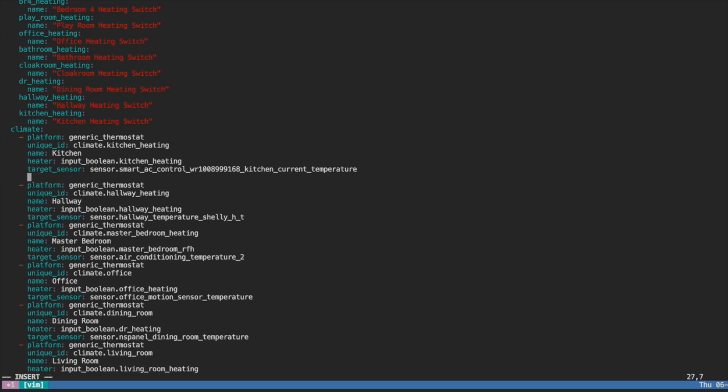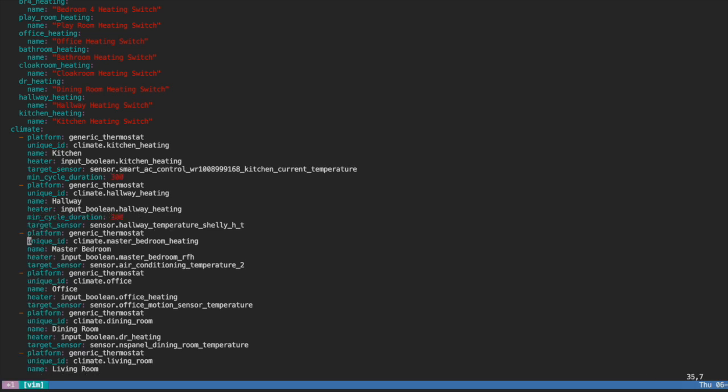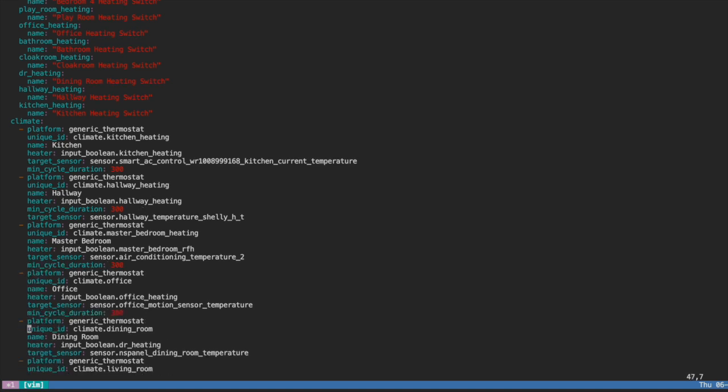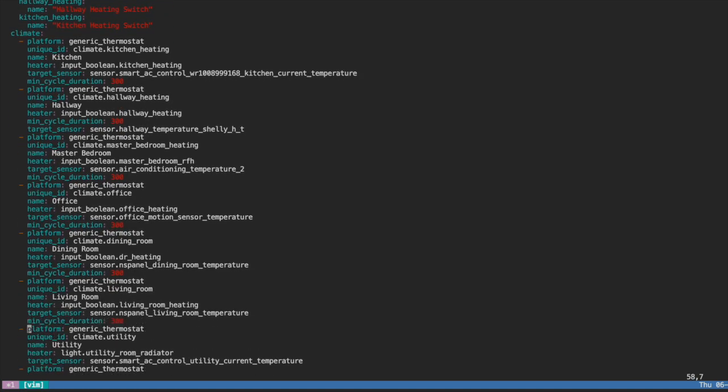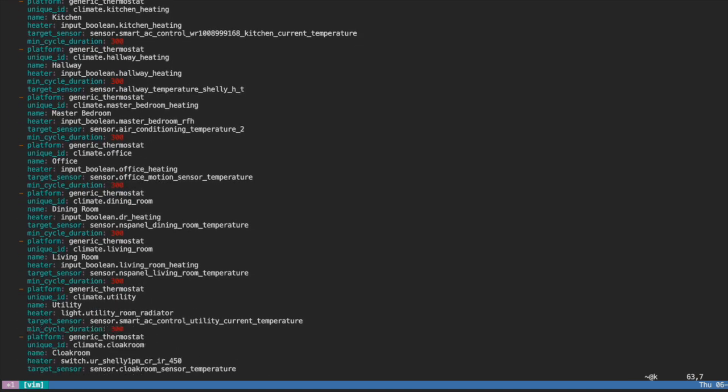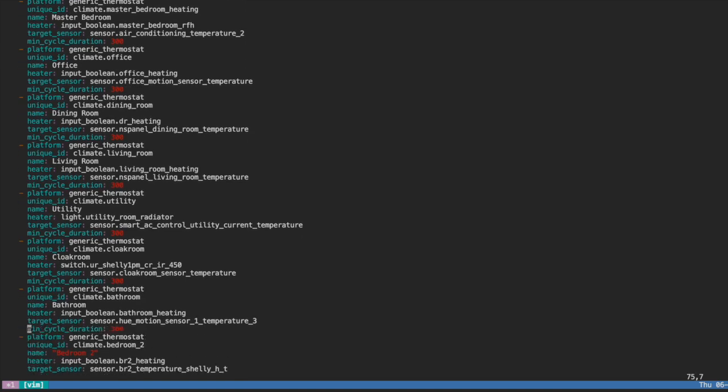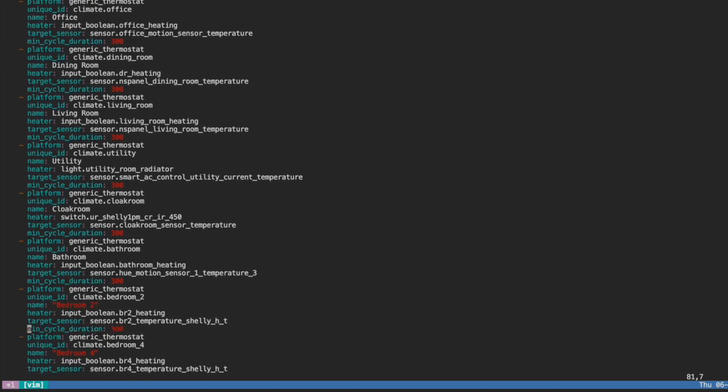Additionally, we've tweaked the heating controls for when panels should be activated. Specifically, we've required a minimum runtime for the units. This is because when there is a reasonable gap between runs of a panel, which we've experienced several times this spring, then the panels often don't warm up to their maximum temperature before the target air temperature in the room is reached.